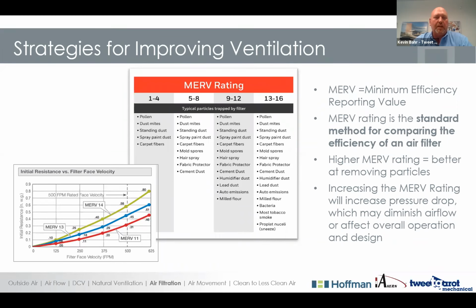It seems like a simple solution, but it can affect the operation of your mechanical equipment, because the higher MERV rating, even though it removes more particles, has quite a bit more pressure drop. If you identify the slide in the lower left corner, it shows the particular MERV ratings, 13, 14, 15, and you'll notice that it can capture more particulate, but the pressure drop increases dramatically. So if you had a conventional air conditioning system and you took a MERV 8 filter out and you put a MERV 14 or 13 in, the pressure drop increases. It'll reduce the airflow across your air conditioning system, and it may cause some mechanical issues or your air conditioning system to potentially freeze up, counteracting everything you were trying to do by increased airflow or more filtration.